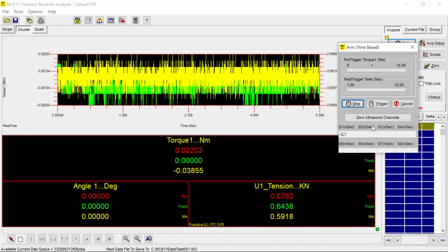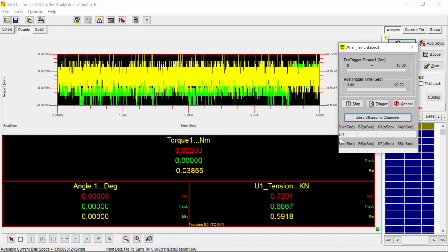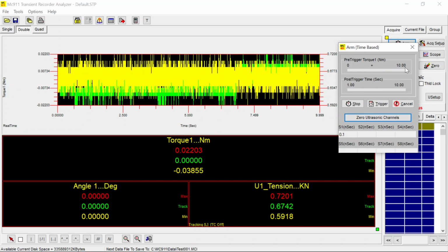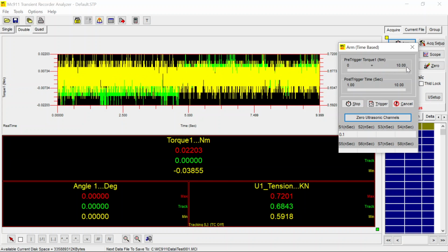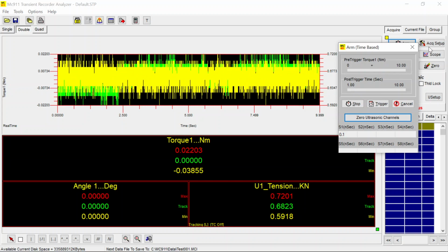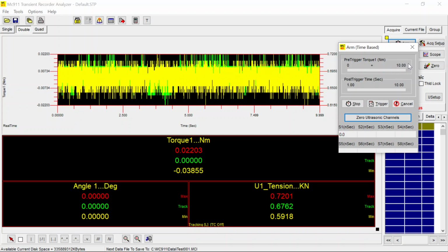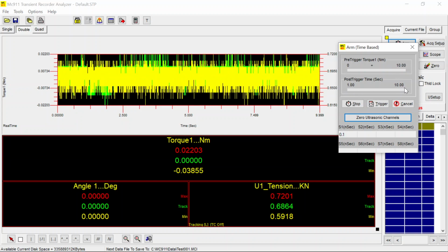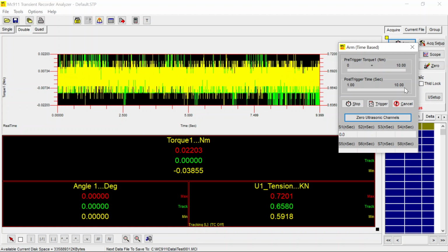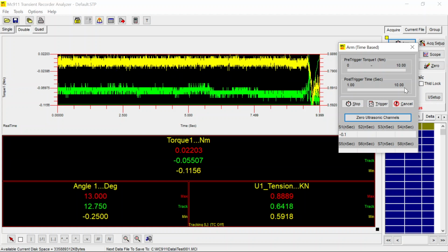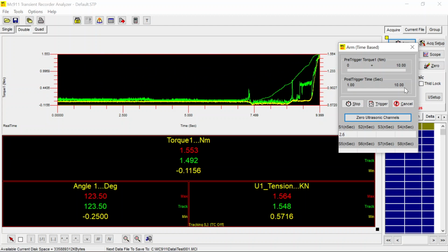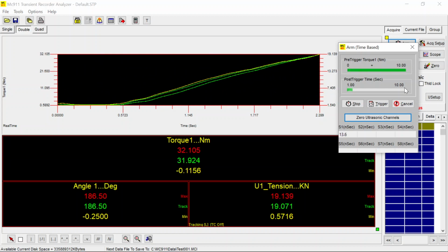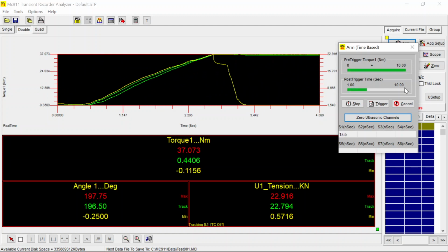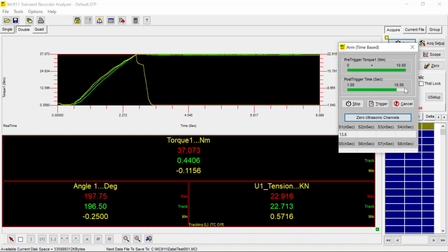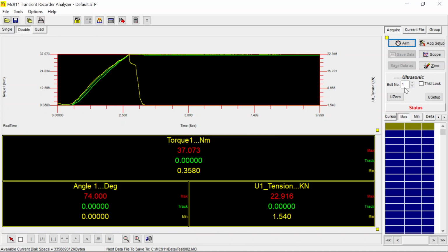You can see you can zero the ultrasonic. Right now it's close to 0. So it's waiting for 10 Newton meter. That's the parameter we set before in this acquired setup. And after that, it will take data for 10 seconds. So I'm going to tighten this bolt. So it triggered and it's taking its time and it's done.